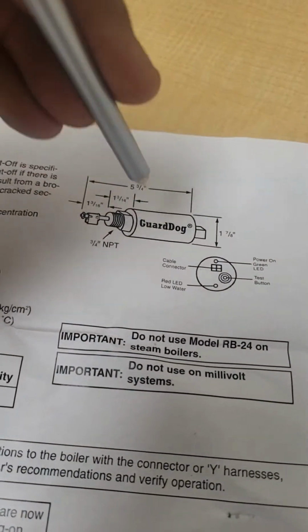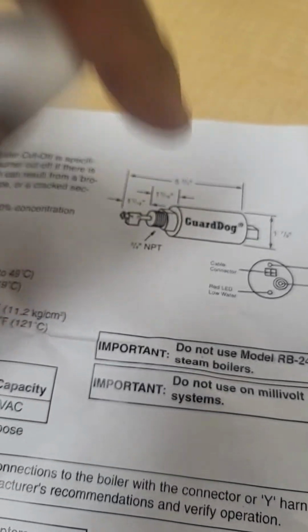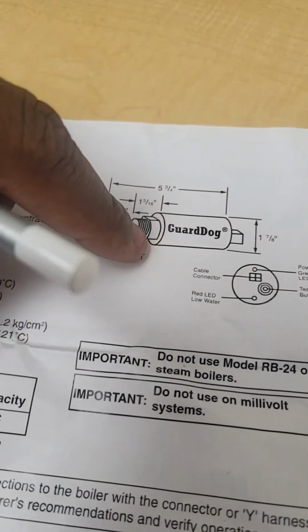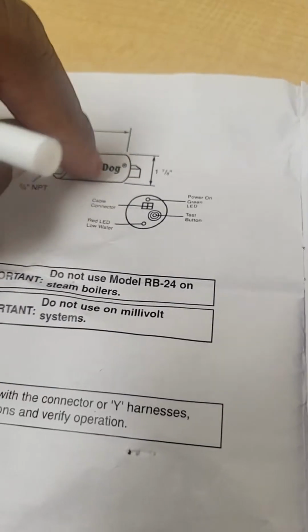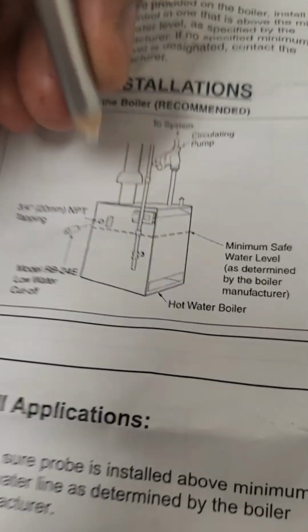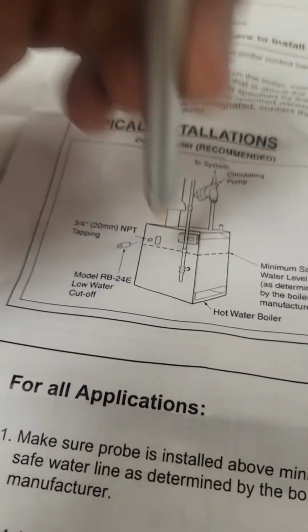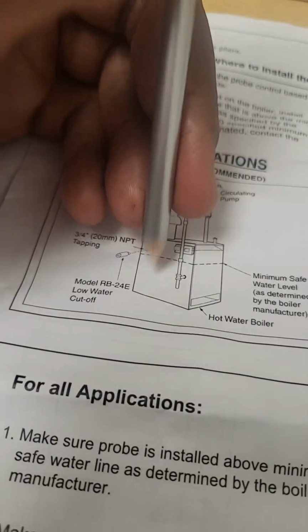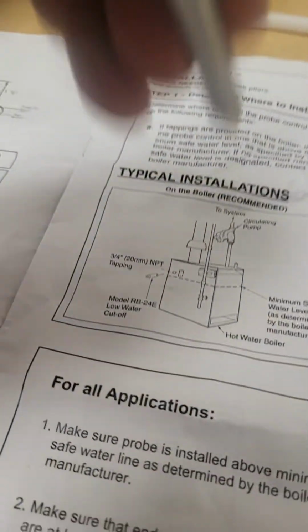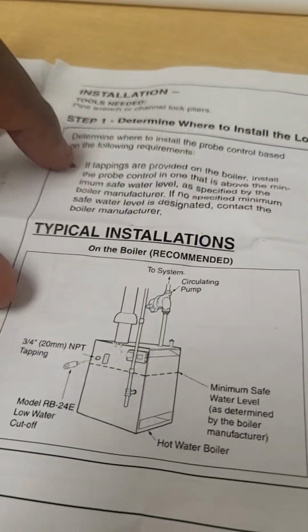On this particular low water cutoff, I had an existing tapping because the old low water cutoff got rusted and shorted out the transformer. Now, if that wasn't the case, and say a township required a low water cutoff on every hot water boiler regardless of age or condition, that's a different scenario. That's what this is referring to.